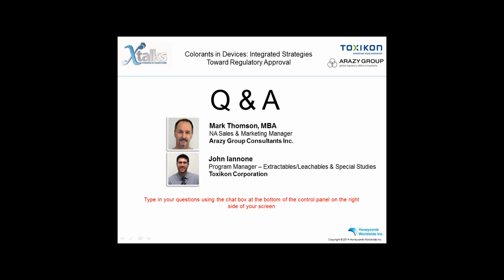Okay. So if you were to choose a colorant that has been approved for a specific application, then the colorant itself is approved for that specific application, but the other additives, the other degradation compounds from the polymer, all of that still will require the assessment of that device for its application. So regarding the biocompatibility that is required for a medical device, I'm not going to say that if you pick a certain colorant that is approved for a specific application, it will minimize your biocompatibility. But certainly it may minimize the additional testing that you need to do specific to the colorant.